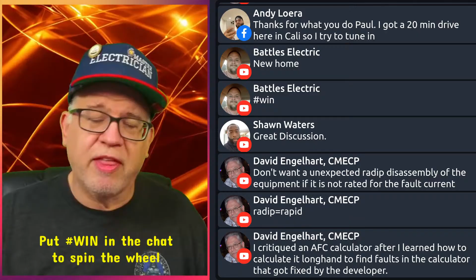That type of thing. So anyway, it's just a common sense thing to me. But it is what it is. The code will tell you when you need the available fault current calculation. When you need that, you do your best to do it. But again, it's more of a common sense approach to me in that scenario. Now, where it can be critical is that some loads also contribute to fault current. So if the service goes out or power stops and you have motors that are running, they all of a sudden turn into generators, right? And so they can contribute current back.